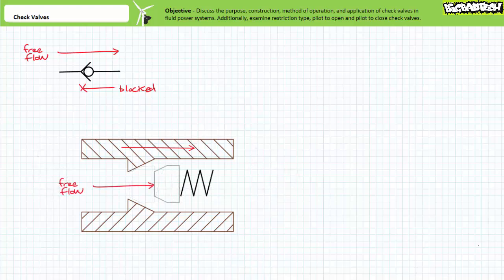Note in the free flow direction, fluid must overcome the force of a light biasing spring. This implies the check valve in the free flow direction isn't exactly free and necessitates a little push. This initial push is known as cracking pressure and is the pressure at which the poppet partially unseats.